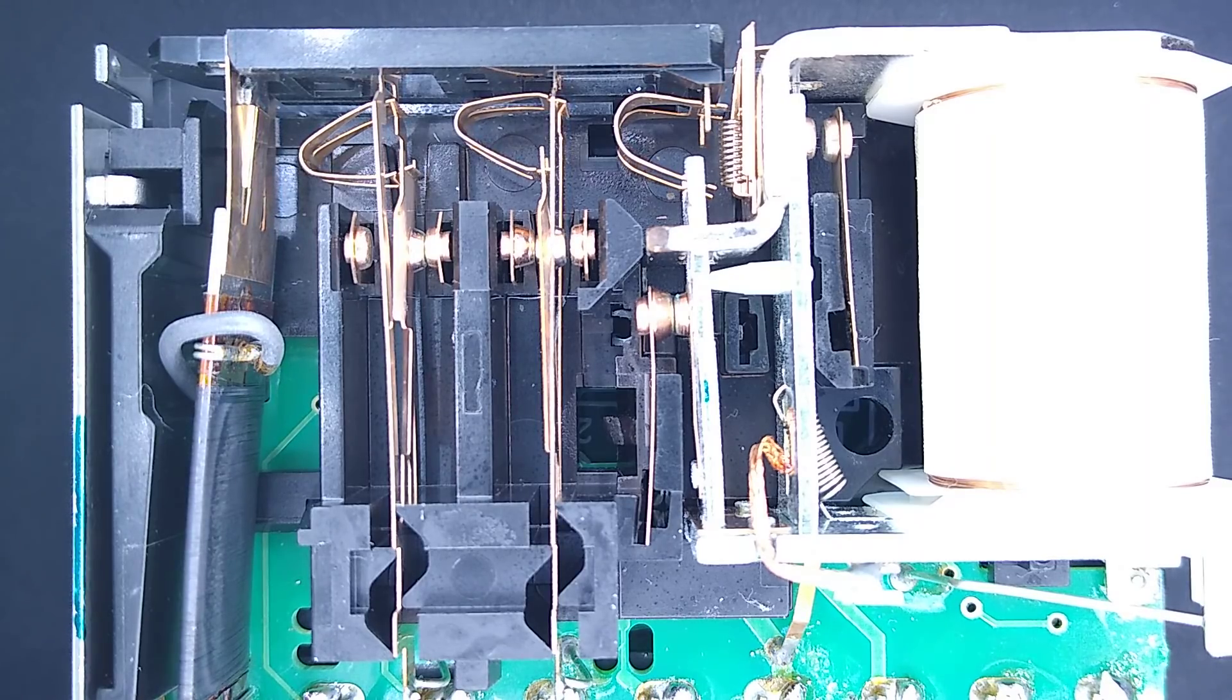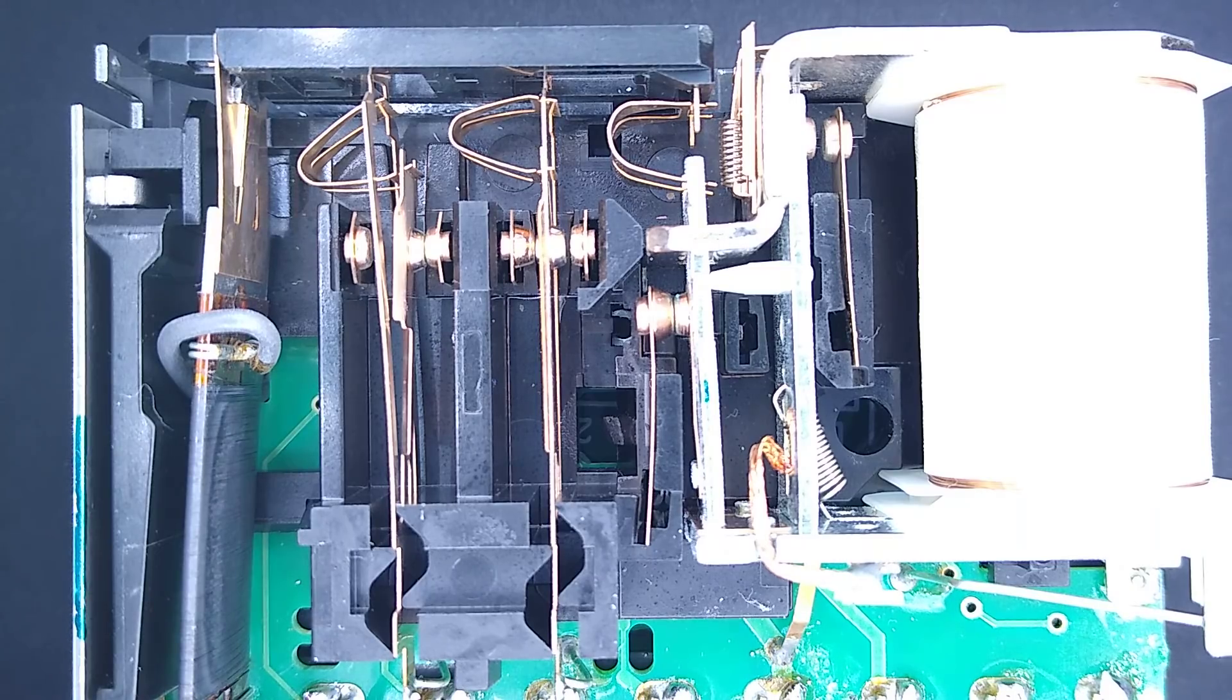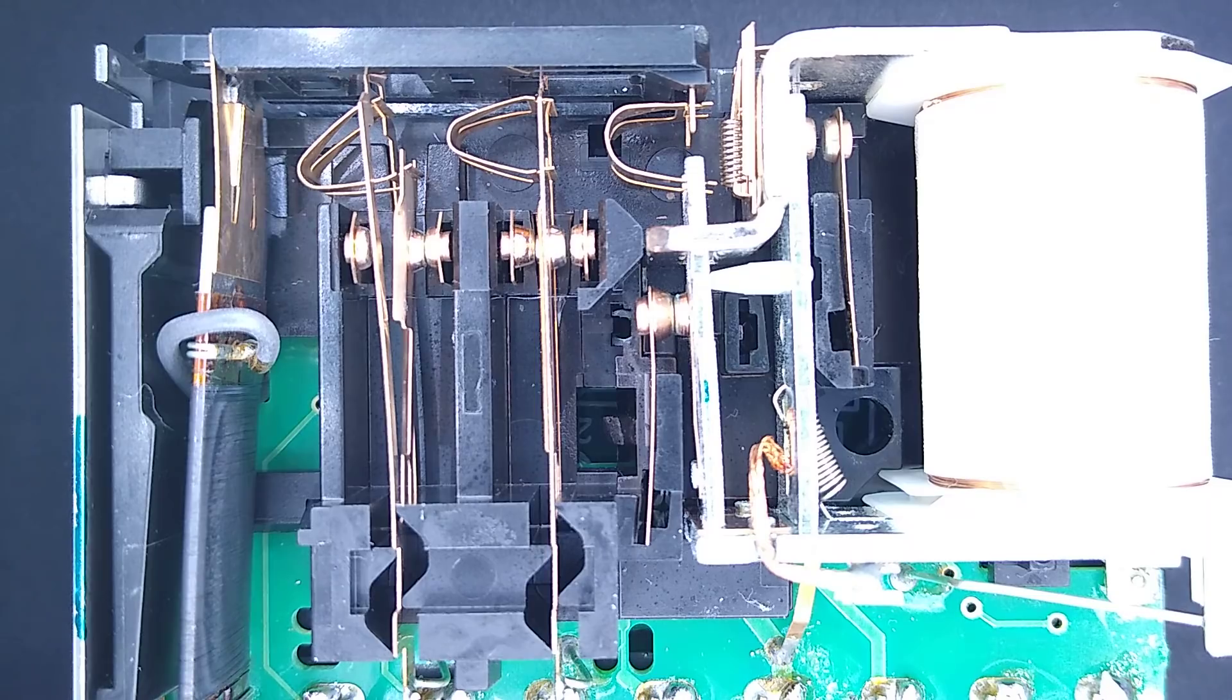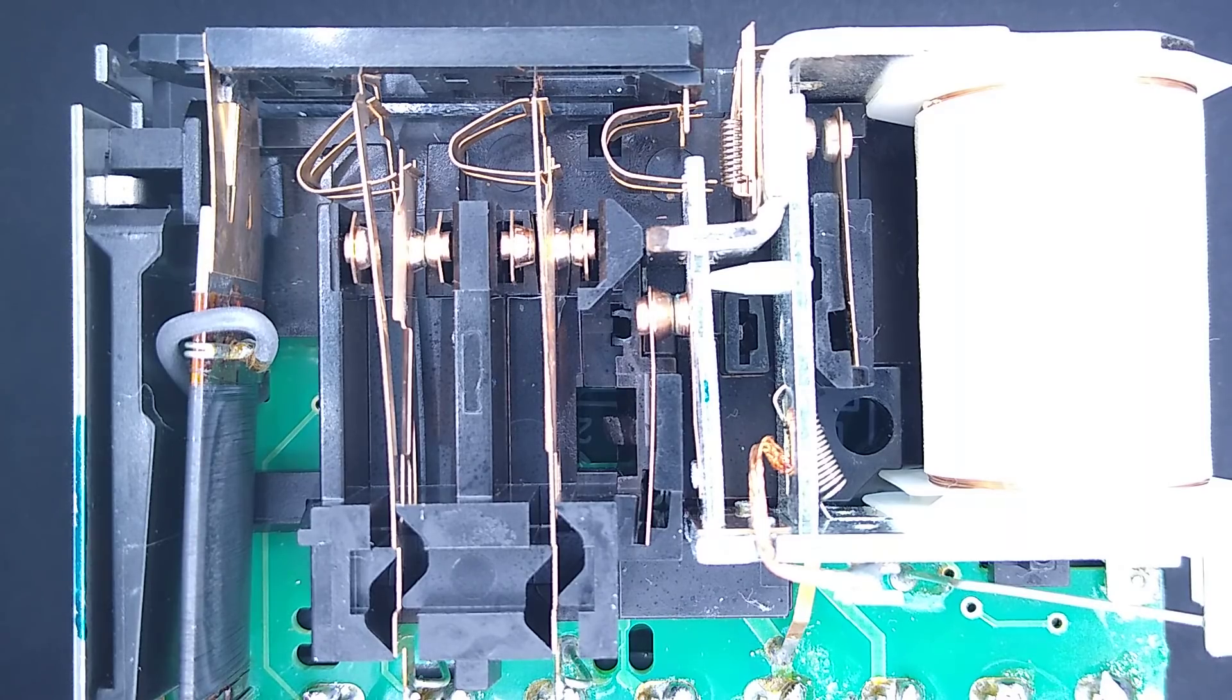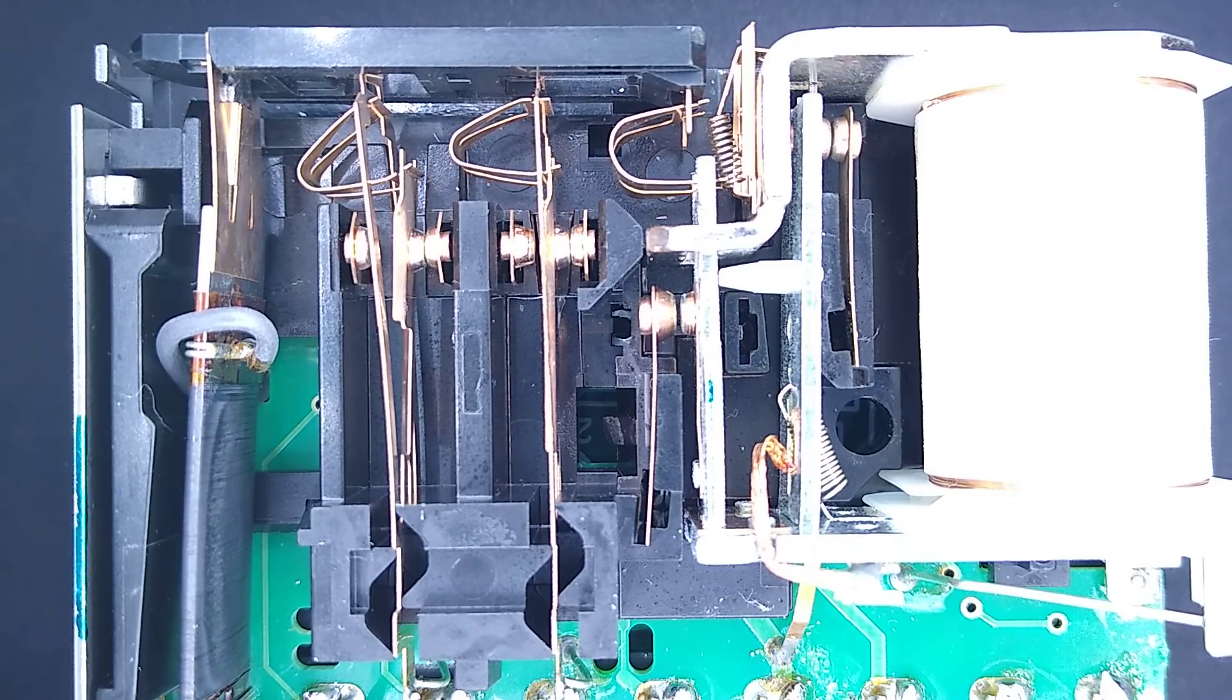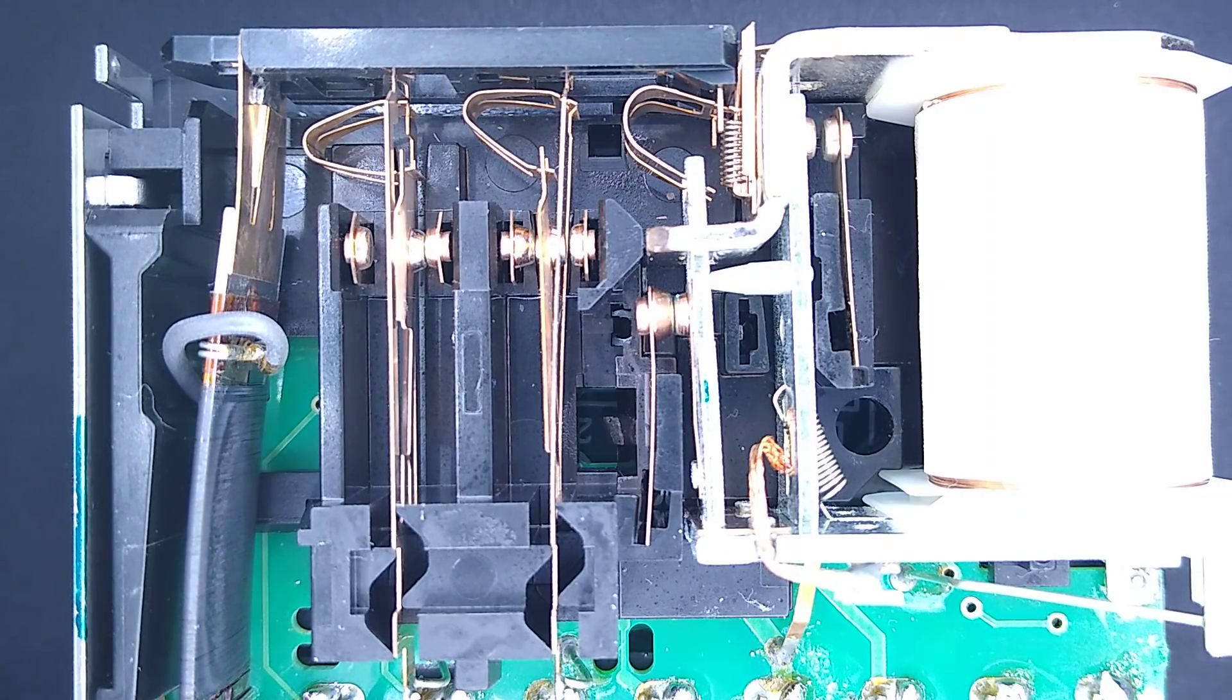And now that actuator, its heater has been deactivated, and also the spark has been turned off at the same time. So it's now reverting back to the other end. As it reverts slowly back to the other end, it resets the oil valve two, which is the middle contact, which now actually has an active live contact thanks to the fact that the oil has been enabled. And it will click over and enable the second oil valve. So it goes up to the second stage of oil injection. If at any point in time the flame goes out, the coil drops out. It kills the oil, enables everything the same sequence again, and tries to actually ignite. And if it succeeds, then it just does the same thing again. And if the oil goes out, if it's intermittent, it will recover to a certain degree.